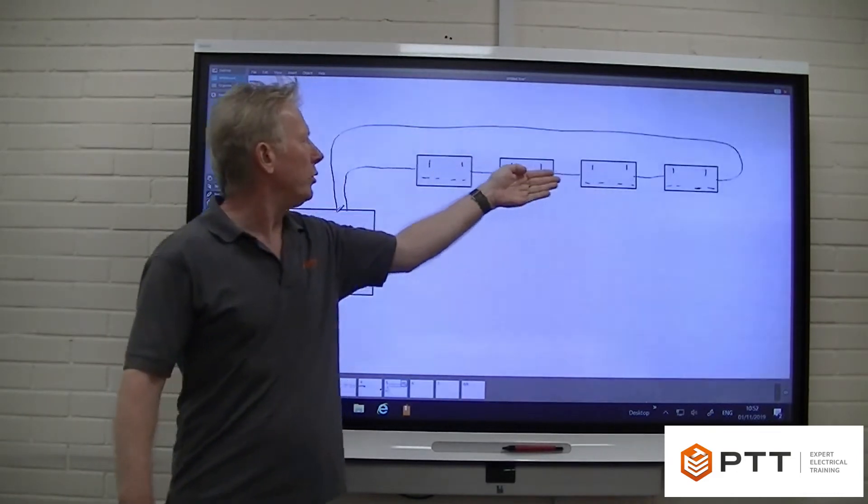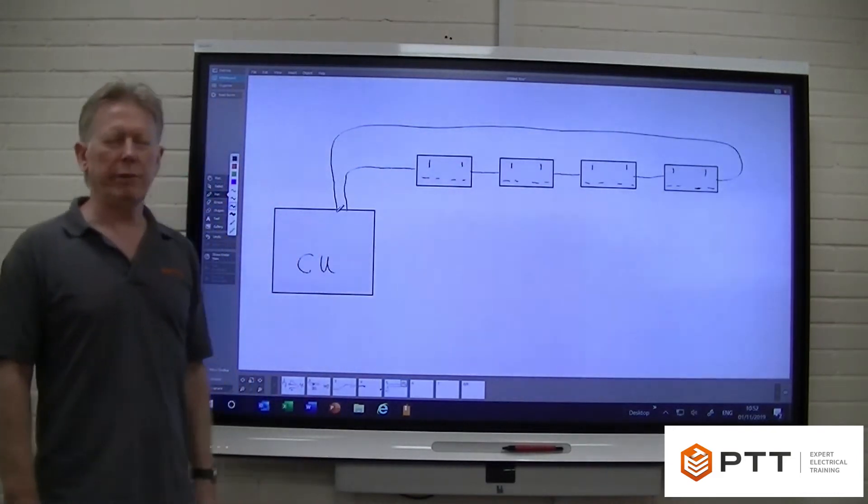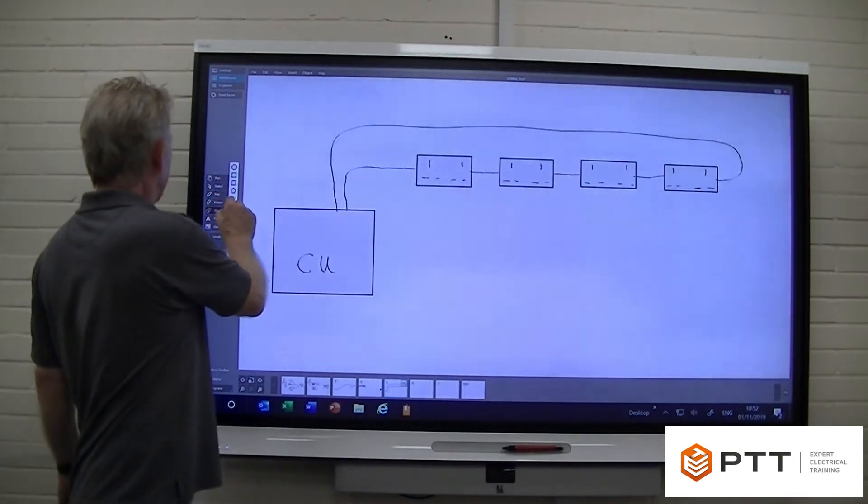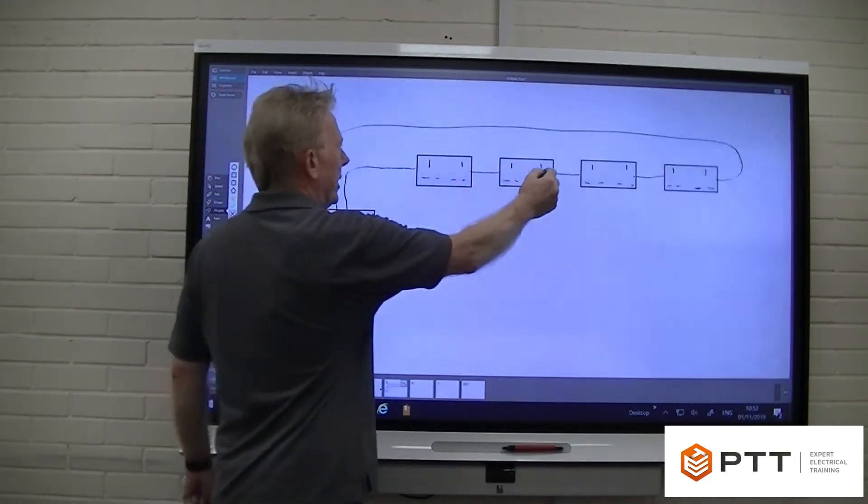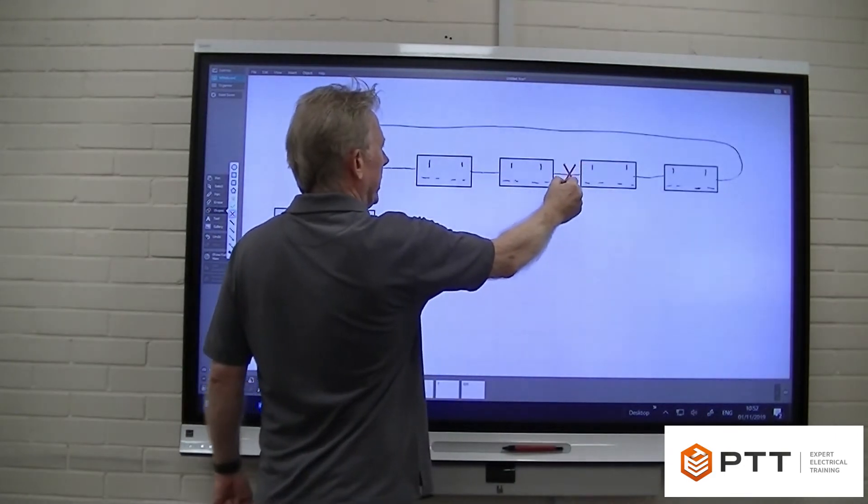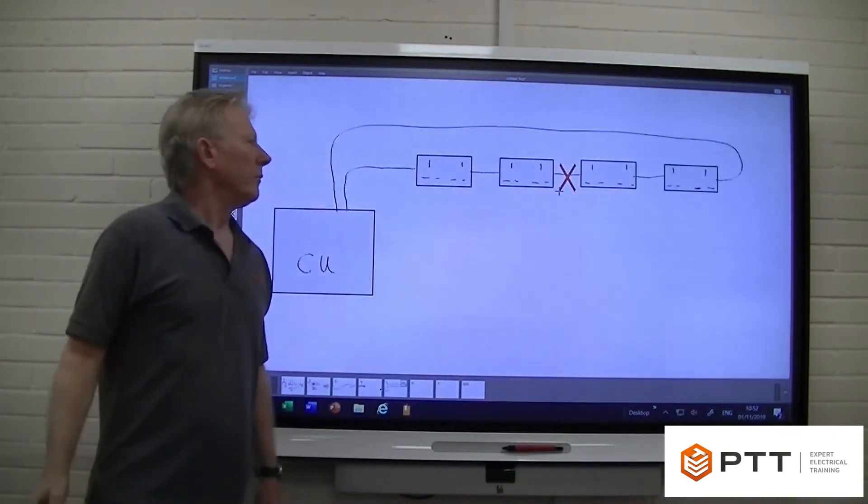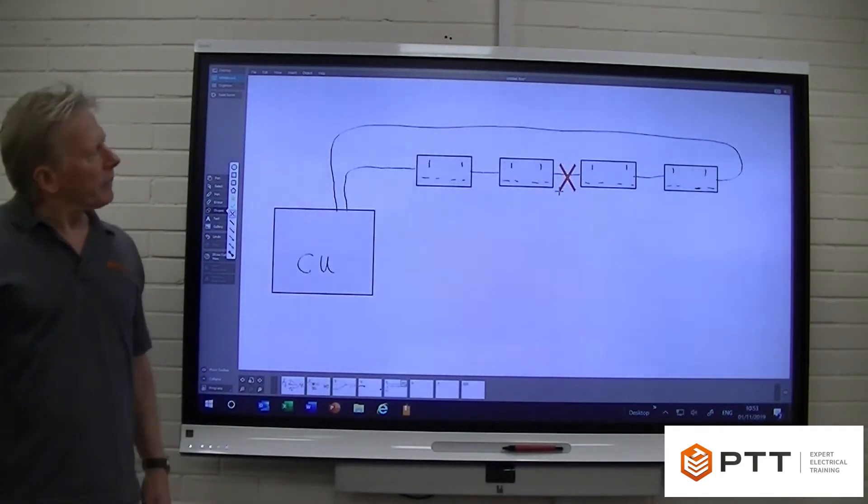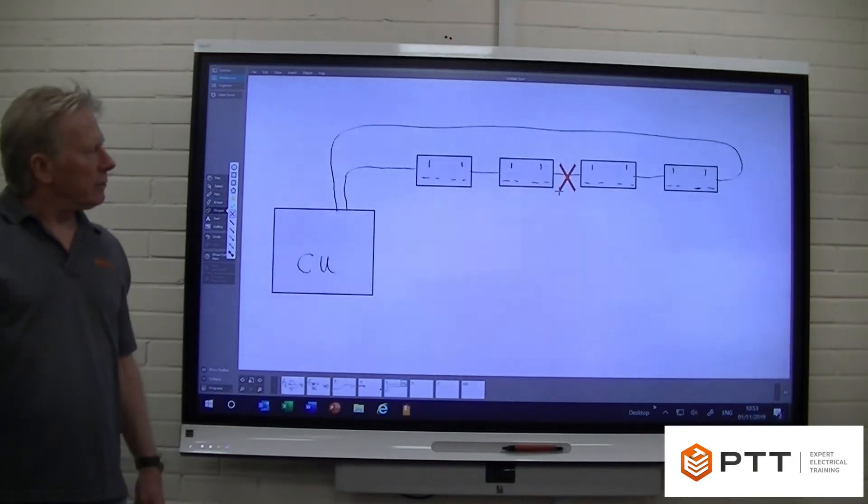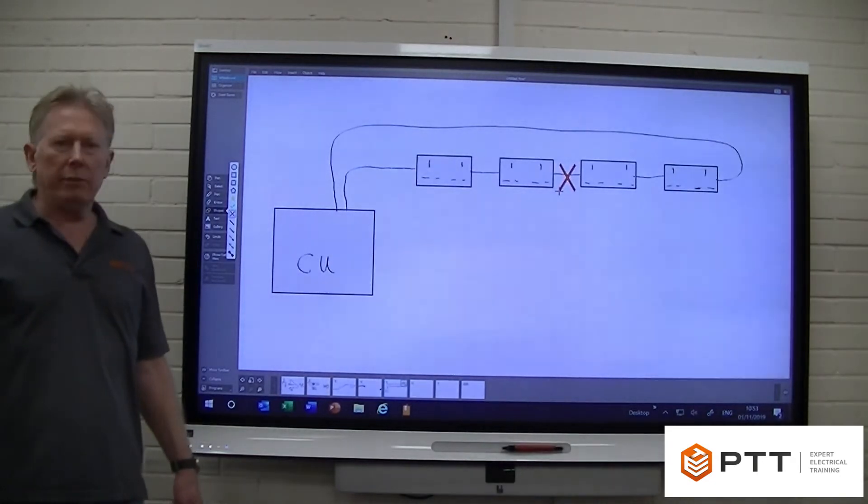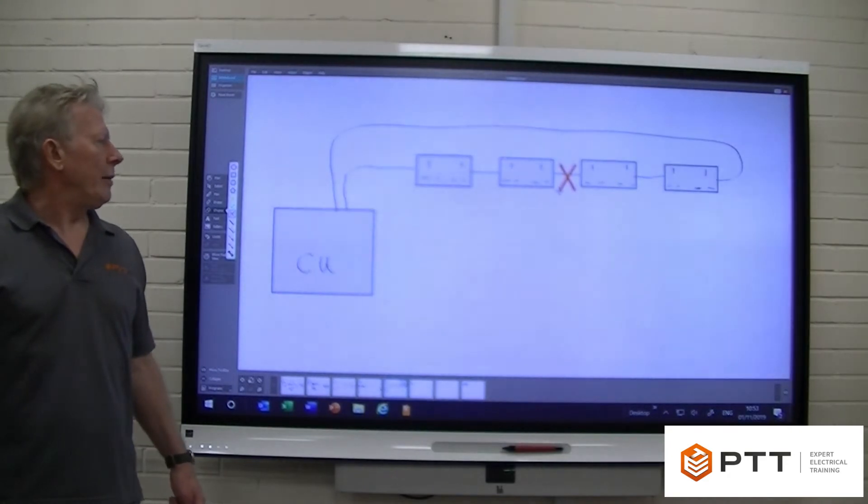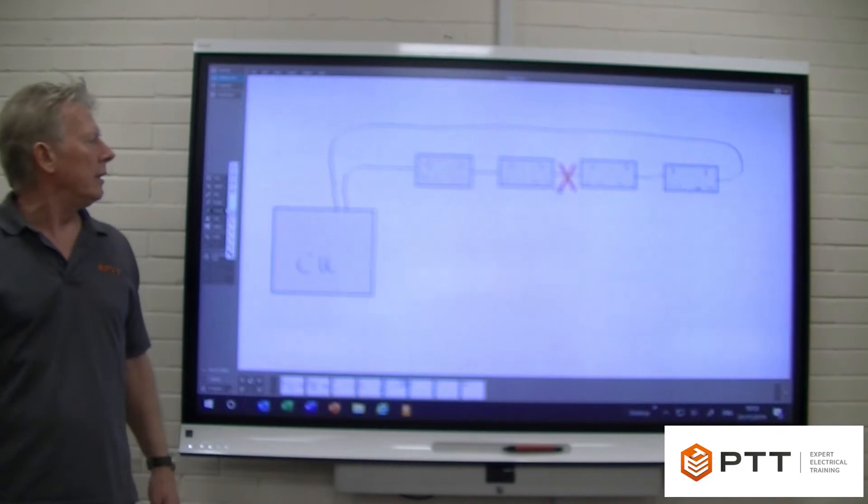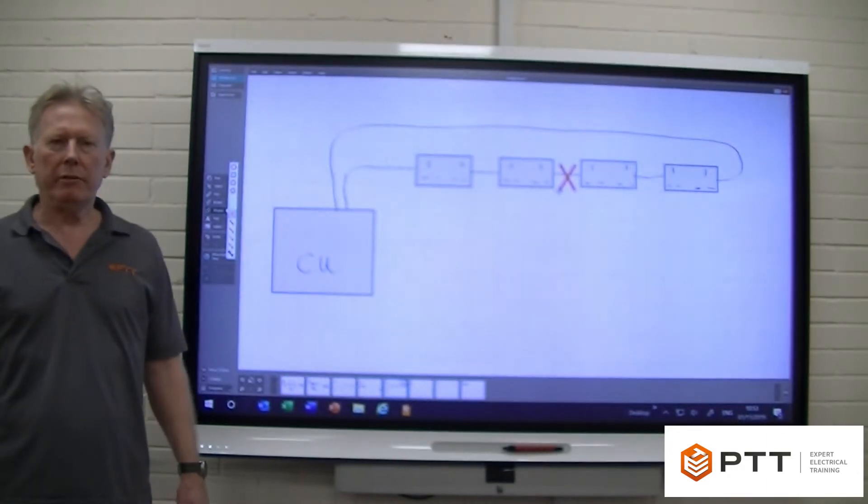And because of this, it's very important that we actually test the ring correctly. Now I'll just demonstrate something. If we were to actually break the ring there for instance, we may not actually be aware of that failure. But now what we've done is we've actually got two radials now which are now protected by our 32 amp breaker, which is too much for the actual cable concerned. So this is where a correct regime of testing actually comes in.